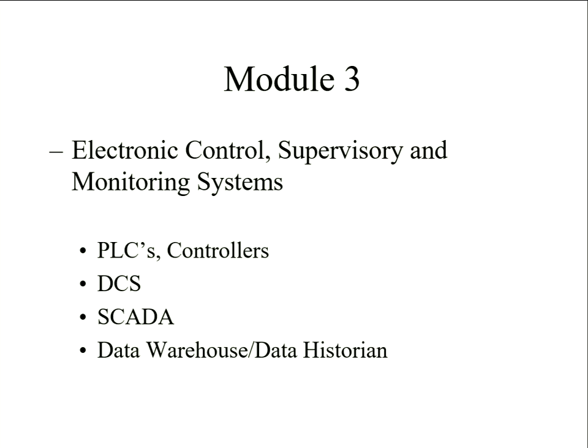So the PLCs and control are typically microprocessor based, so they will implement the control algorithms I was talking about in the previous session. There's all sorts of hardware. All sorts of manufacturers will sell these sorts of boxes to you. In some cases you can set functional software, high level logic. You can do flow computations in your flow controller, so it might have some functional logic in there. Sequential control, so you could do A then B then C.